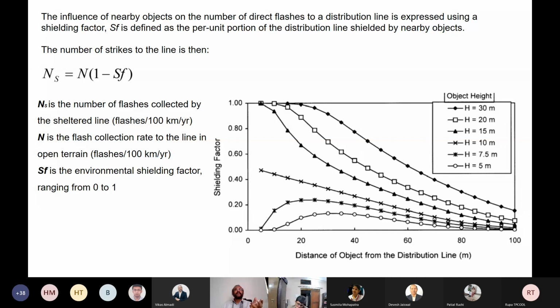What we found is that although the lightning density in the areas where these distribution lines run is quite small, the damage to these pole-mounted transformers was very high. The reason was the number of lightning flashes: say, for example, there are only 5 lightning flashes per square kilometer per year, a rather small value.